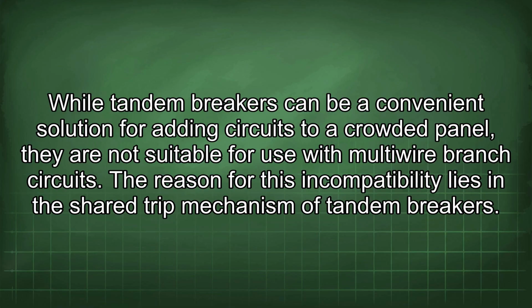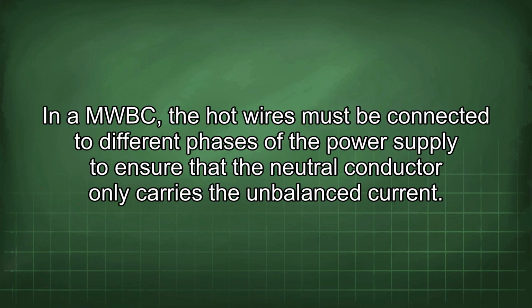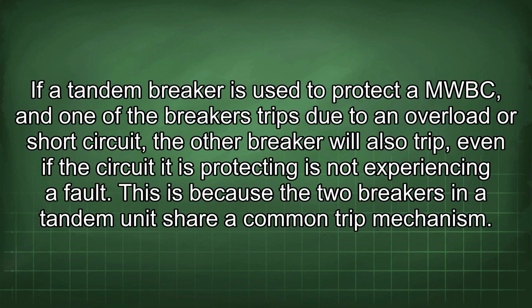The reason for this incompatibility lies in the shared trip mechanism of tandem breakers. In a MWBC, the hot wires must be connected to different phases of the power supply to ensure that the neutral conductor only carries the unbalanced current. If a tandem breaker is used to protect an MWBC and one of the breakers trips due to an overload or short circuit, the other breaker will also trip, even if the circuit it is protecting is not experiencing a fault. This is because the 2 breakers in a tandem unit share a common trip mechanism.